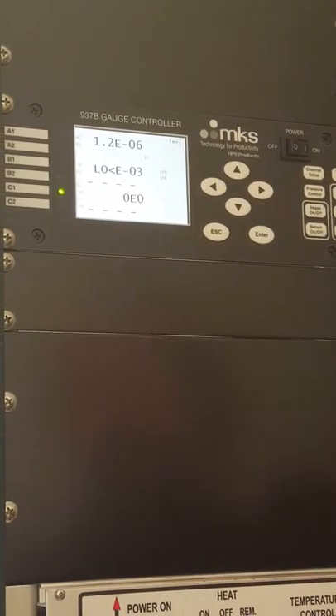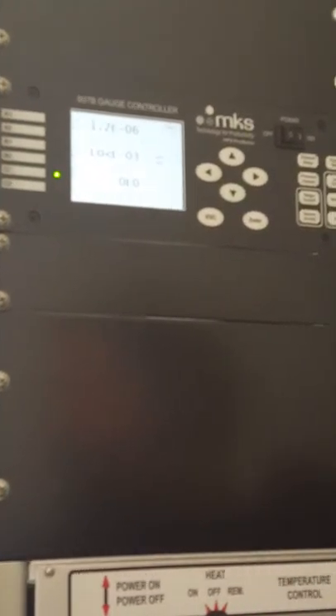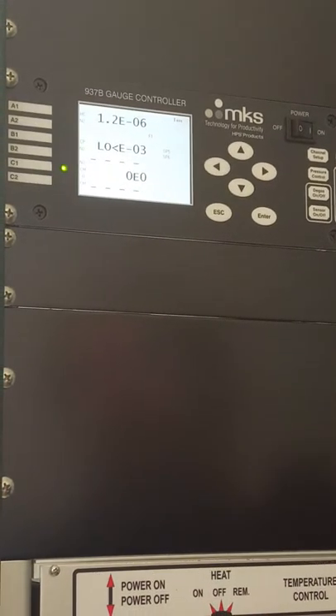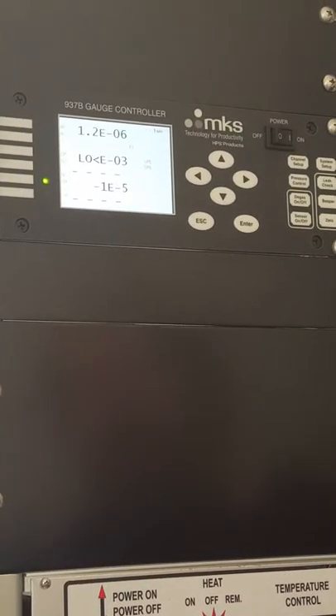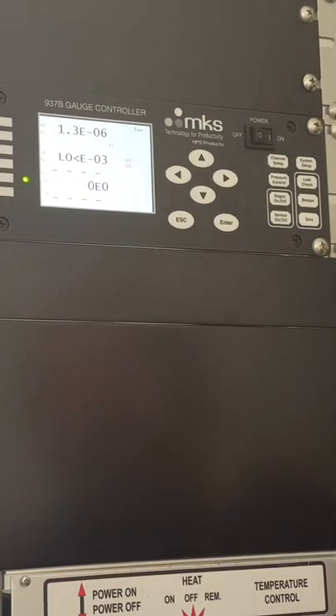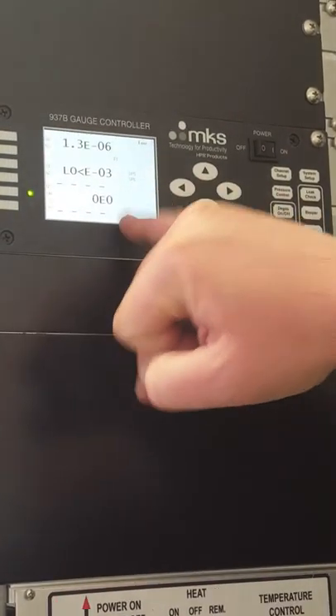That's the only thing to do with that third gauge. But this one is probably the most critical gauge to zero because that's your process gauge.